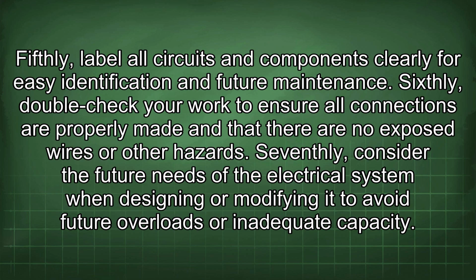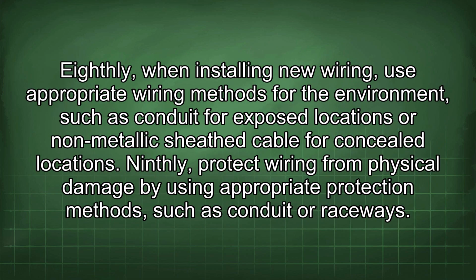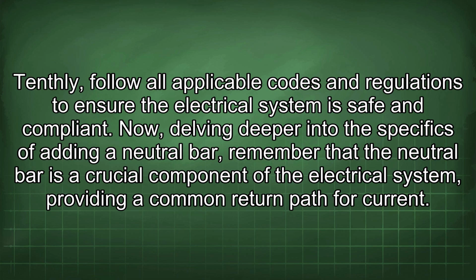Sixthly, double-check your work to ensure all connections are properly made and that there are no exposed wires or other hazards. Seventhly, consider the future needs of the electrical system when designing or modifying it to avoid future overloads or inadequate capacity. Eighthly, when installing new wiring, use appropriate wiring methods for the environment, such as conduit for exposed locations or non-metallic sheath cable for concealed locations. Ninthly, protect wiring from physical damage by using appropriate protection methods, such as conduit or raceways. Tenthly, follow all applicable codes and regulations to ensure the electrical system is safe and compliant.